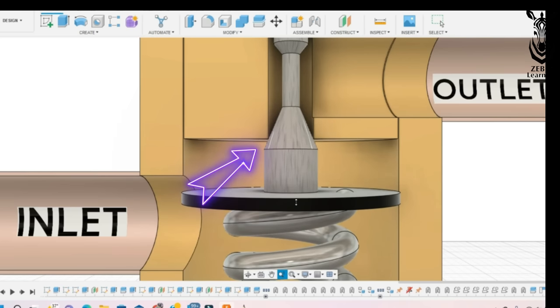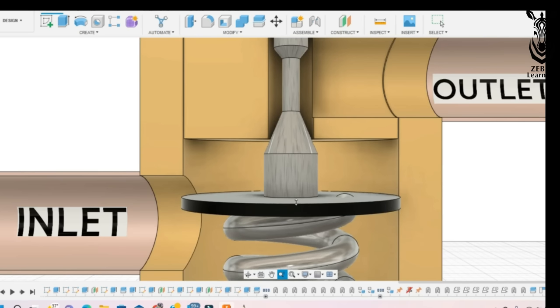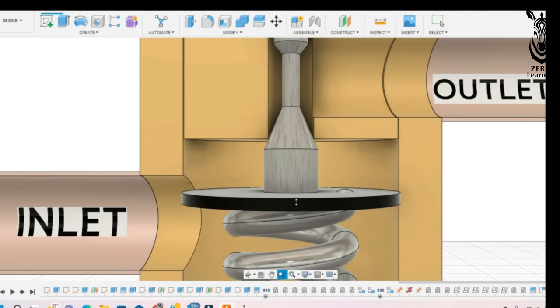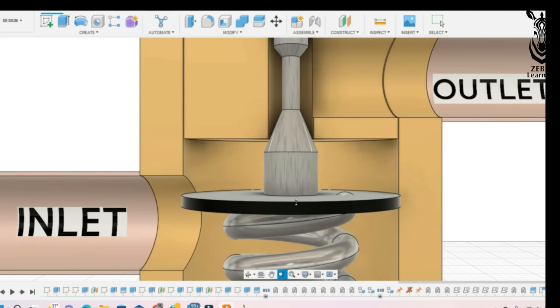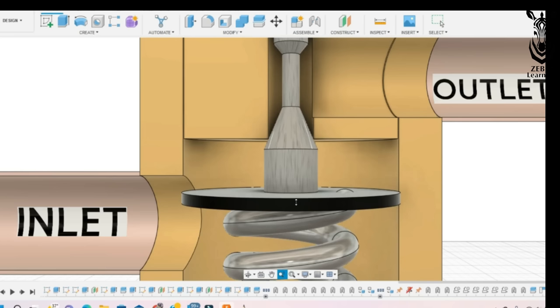And one more point is that when this passage for refrigerant is closed, it does not close completely. There is a small gap through which a small amount of refrigerant continues to flow. Only when the temperature of the evaporator increases, this gap increases, and more refrigerant goes to the evaporator.